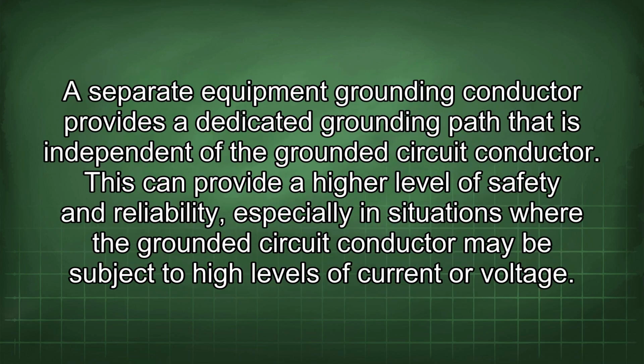A separate equipment grounding conductor provides a dedicated grounding path that is independent of the grounded circuit conductor. This can provide a higher level of safety and reliability, especially in situations where the grounded circuit conductor may be subject to high levels of current or voltage.